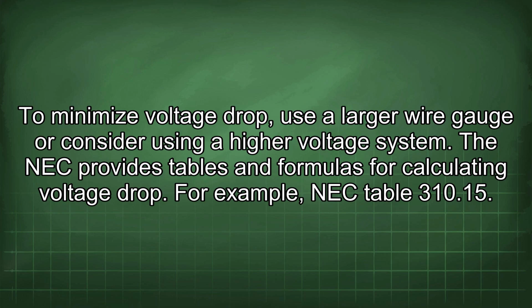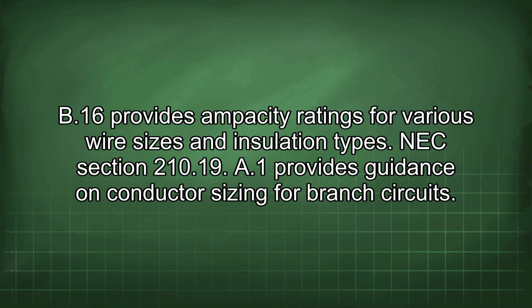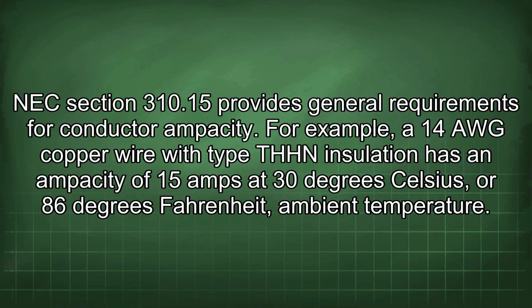The NEC provides tables and formulas for calculating voltage drop. For example, NEC Table 310.15(B)(16) provides ampacity ratings for various wire sizes and insulation types. NEC Section 210.19(A)(1) provides guidance on conductor sizing for branch circuits. NEC Section 310.15 provides general requirements for conductor ampacity.